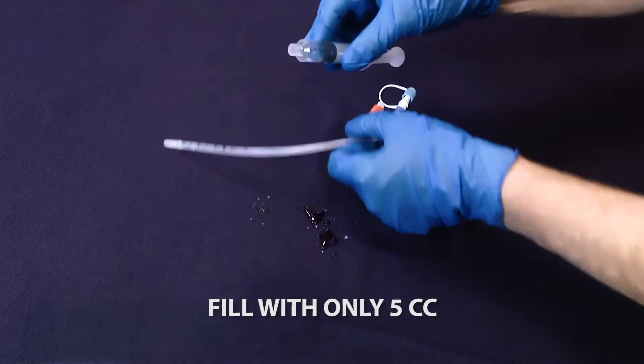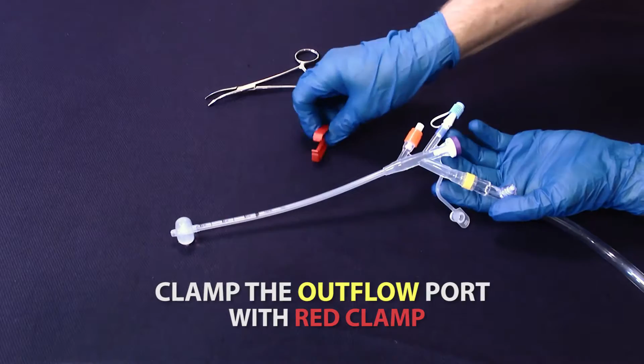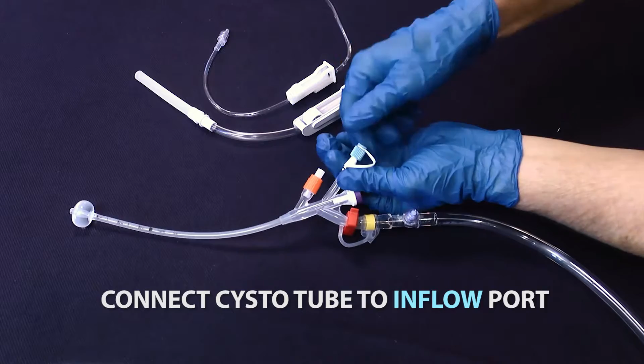When it is time for the cystoscopic portion of the procedure, remember these key steps. 1. Clamp or plug the yellow outflow port. 2. Instill fluid through the blue inflow port using either catheter tubing or IV tubing with a Luer lock connection. It is helpful to keep the roller clamp sterile and closed and close to the irrigation port for better control.